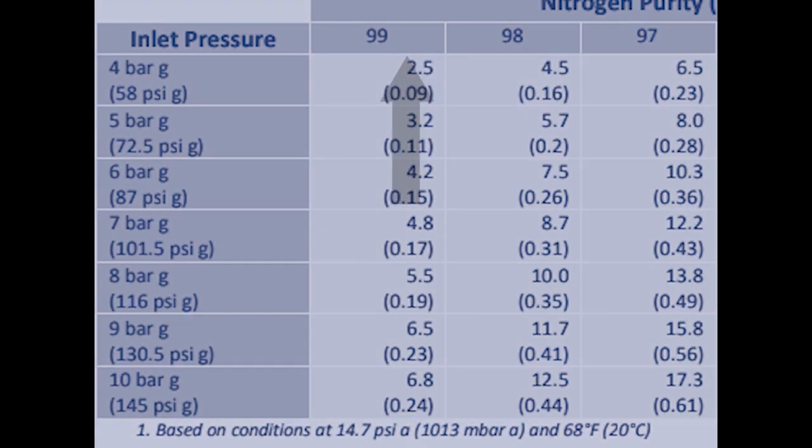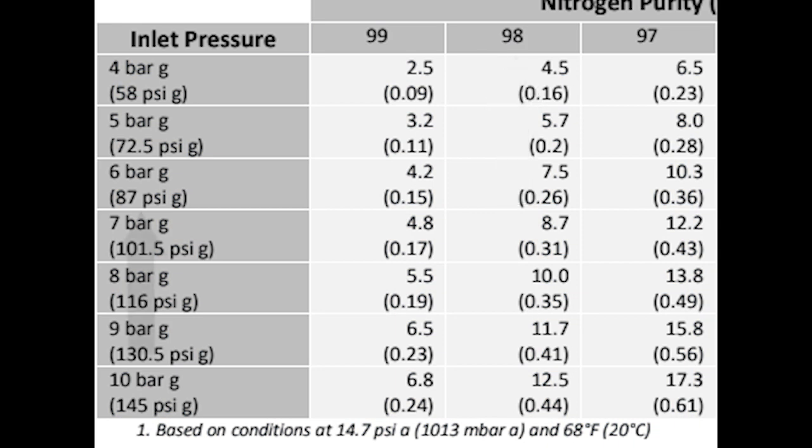For example, if your application requires 98% purity, you would need to set the generator to 87 psi at 7.5 liters per minute.